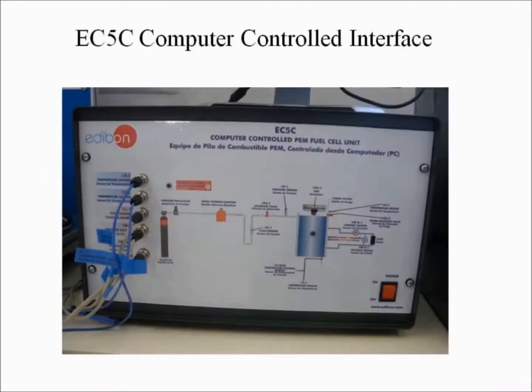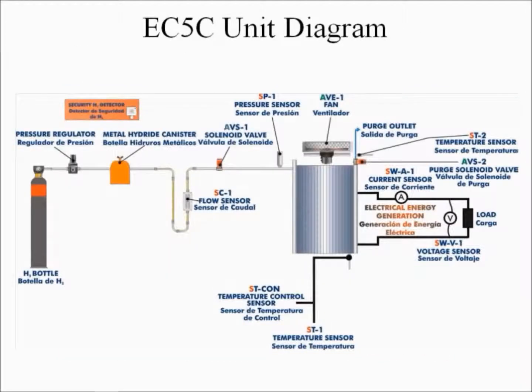All information from the unit passes through the interface box before going to the computer. On the front panel of the interface, we can find the on-off switch for the unit, temperature sensor inputs, flow sensor input, pressure sensor input, current sensor and voltage sensor input, security hydrogen detector light, and a light indicating that the fuel cell stack has started functioning. A unit diagram, which represents the distribution of the different components, is included on the main unit and on the front panel of the computer-controlled interface.